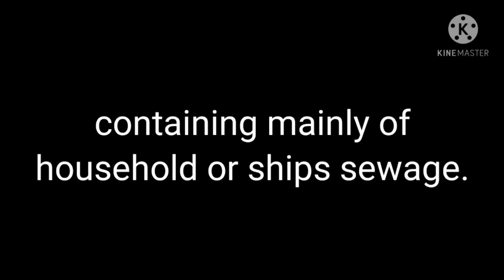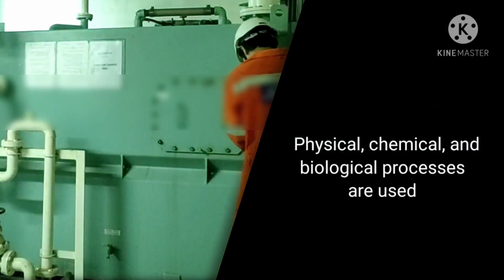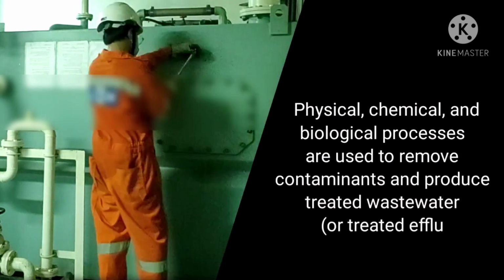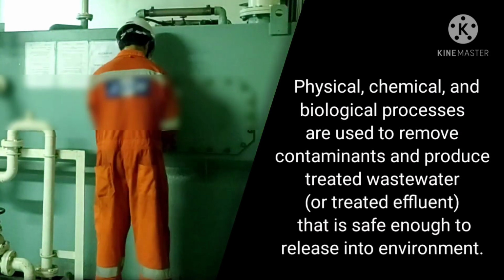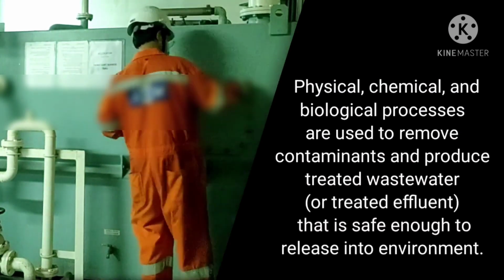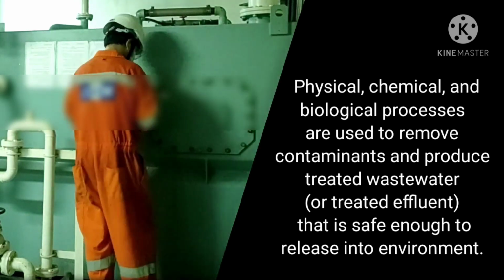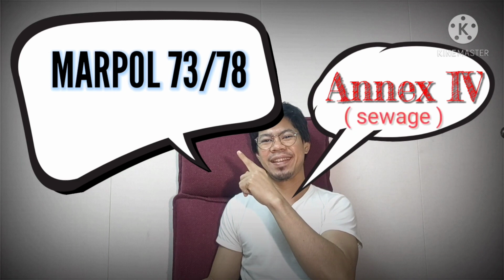A sewage treatment plant is a system for treating domestic waste, containing mainly household or ship's sewage. Physical, chemical, and biological processes are used to remove contaminants and produce treated wastewater called effluent, which is safe enough to release into the environment. On ships, sewage is regulated by Annex 4 of MARPOL 73/78.